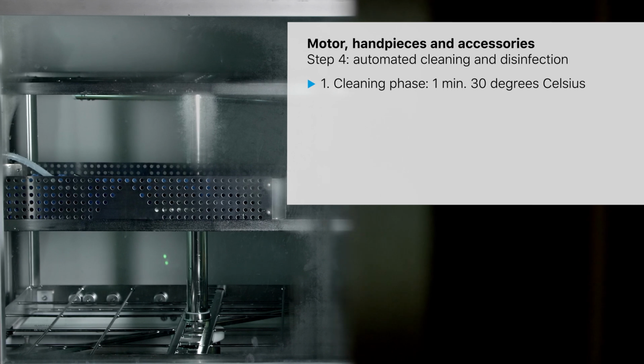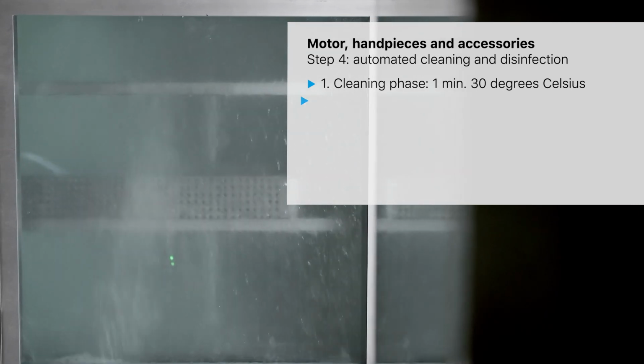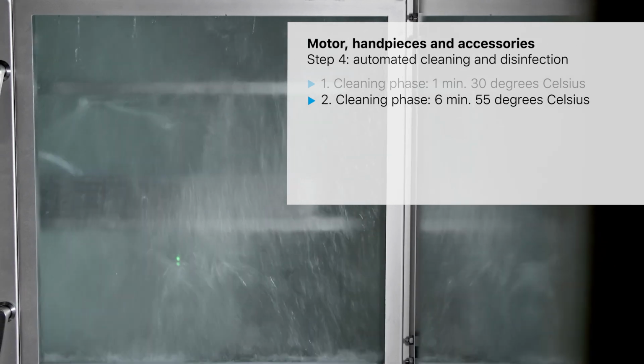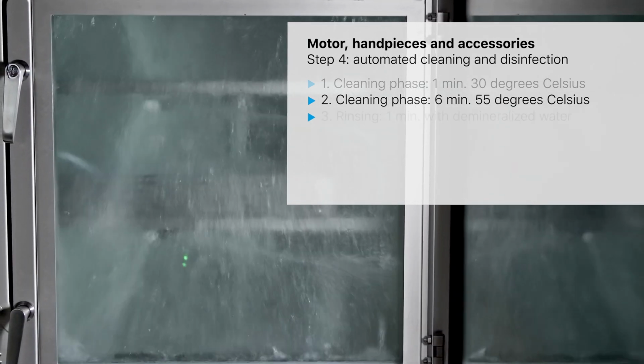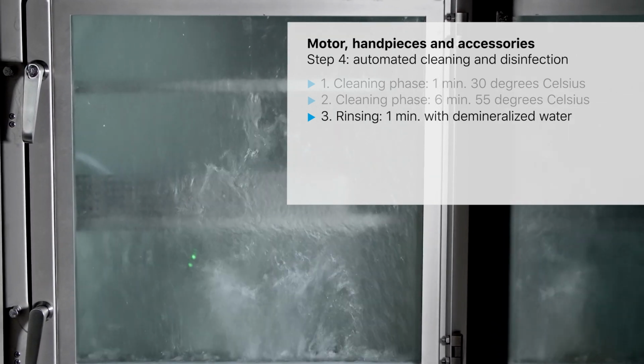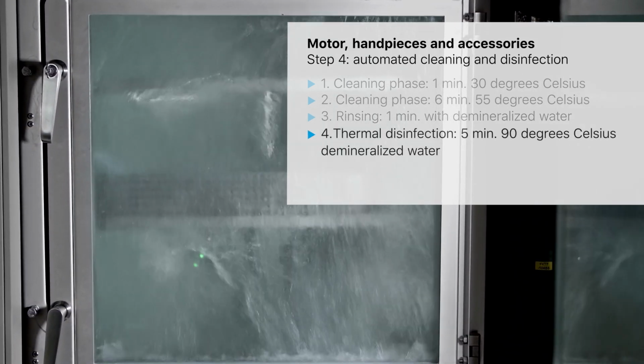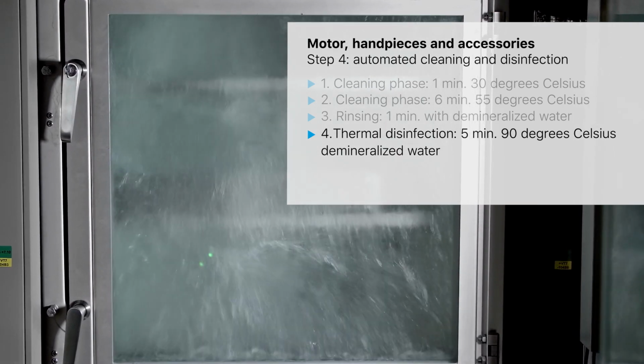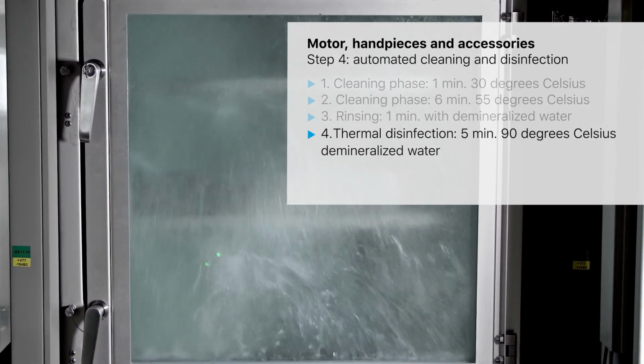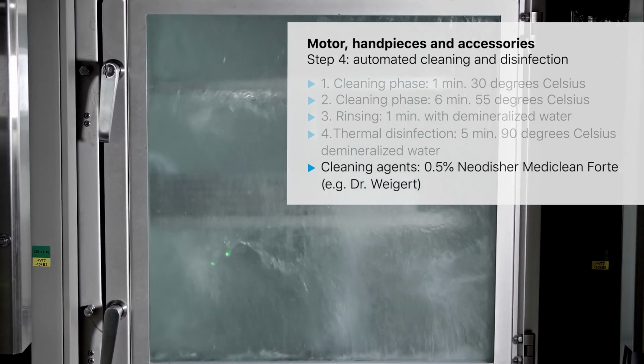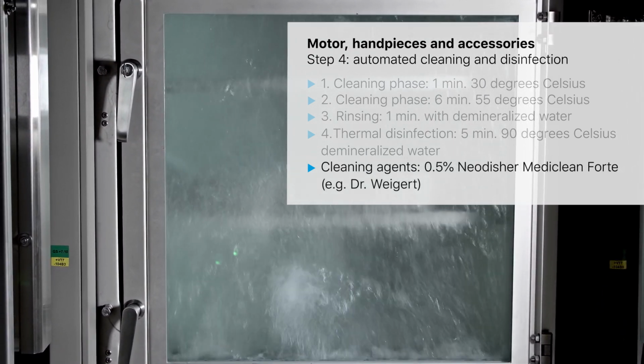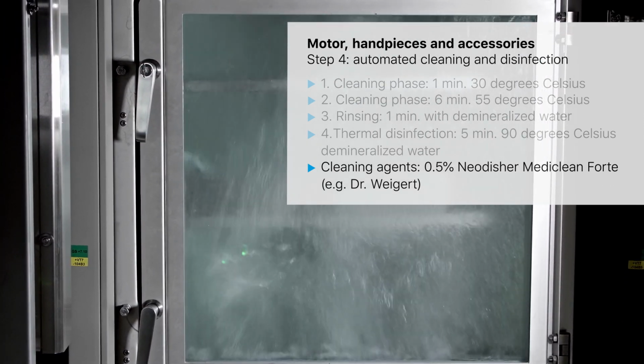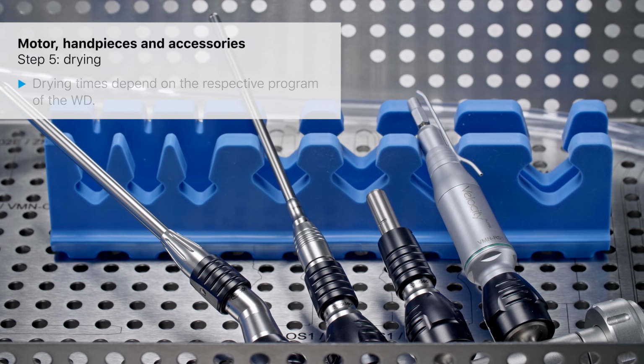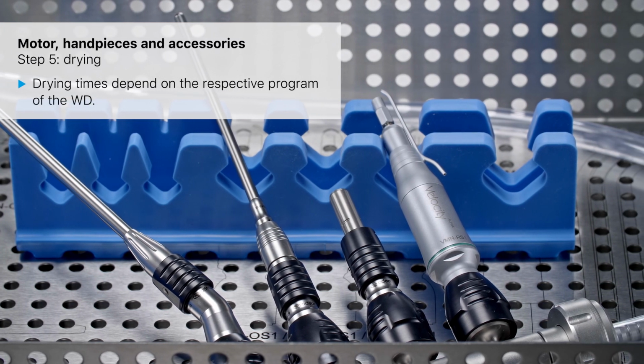One, cleaning phase, 1 minute, 30 degrees Celsius. 2, cleaning phase, 6 minutes, 55 degrees Celsius. 3, rinsing, 1 minute, with demineralized water. 4, thermal disinfection, 5 minutes, 90 degrees Celsius demineralized water. Cleaning agents, 0.5% Neodisher Mediclean Forte, e.g. Dr. Weigert. Drying times depend on the respective program of the WD.